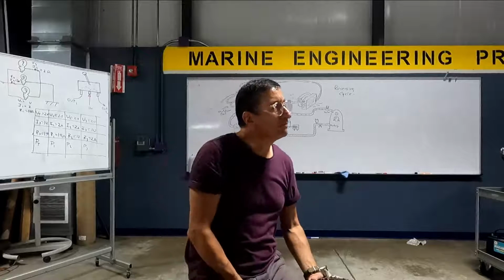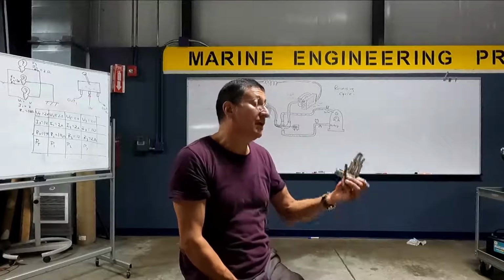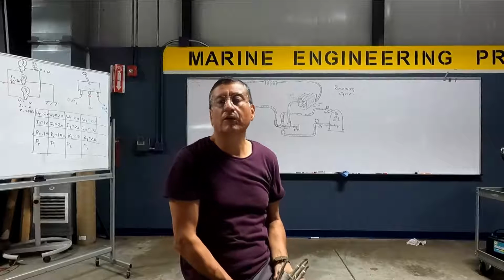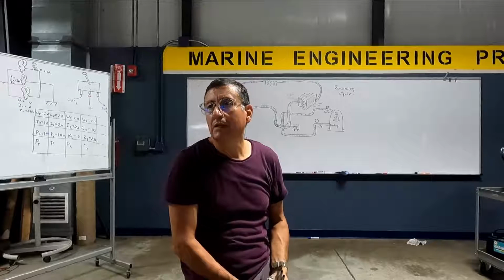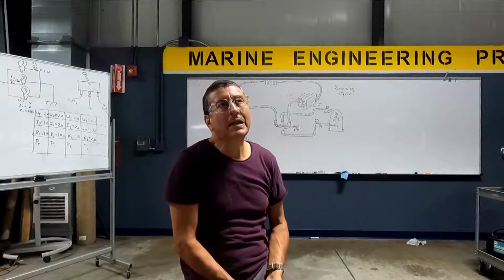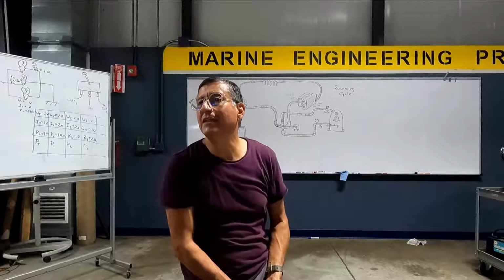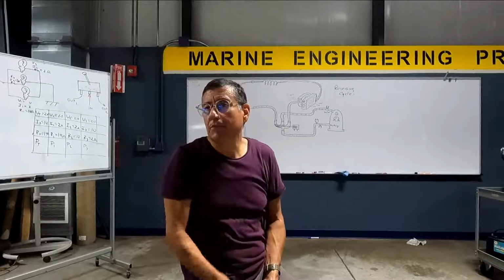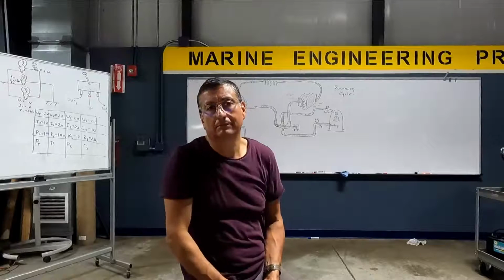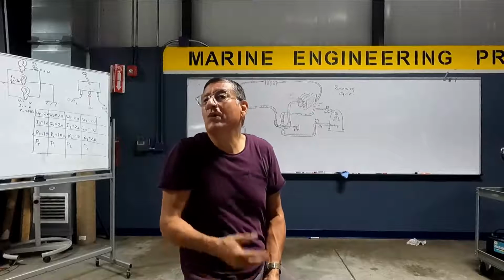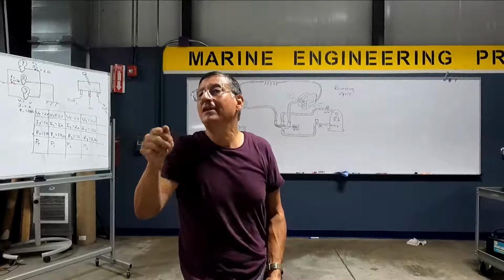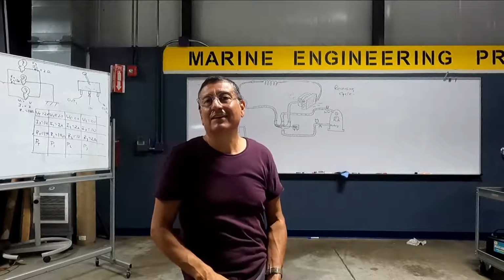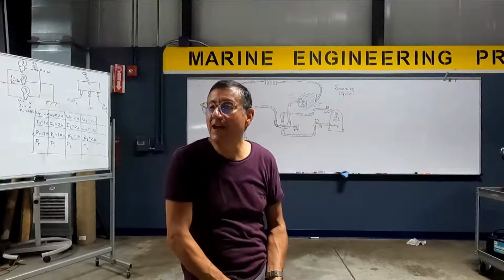If those solenoids go bad, you have to replace them. You have to cut the pipes. Pay attention. It's very common that this solenoid be damaged, for example here in Florida, because here in Florida practically we never use the heating mode. Sporadically, one or two days per year. And when you decide to use the heating mode, the solenoid is stuck and doesn't work. It's very, very common.